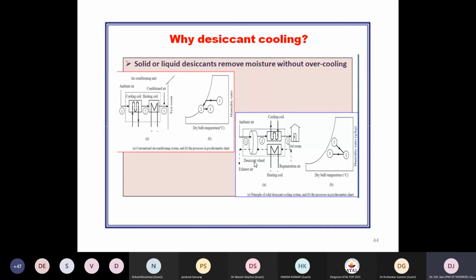So by nature, desiccant, by its pressure variation, has an affinity with moisture. Wherever you put desiccant in a high moisture region, it tries to abstract out the moisture. When that desiccant is laid over a matrix in a rotary wheel, it is called a desiccant dehumidifier. There is also a conventional desiccant normally found in our houses, called salt.